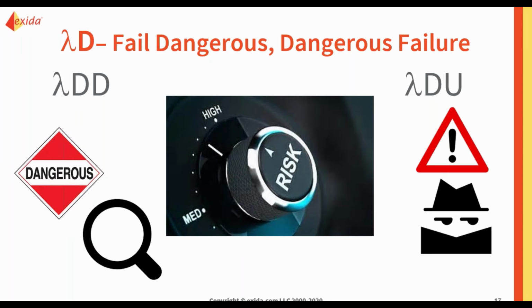What if you have a pressure sensor that is not working and it's high pressure, supposed to shut down the system? It goes over that pressure, you don't know about it. You could have a valve getting stuck in an open on-trip application. It hasn't been used in too long, corroded shut. It needs to close, can't. What about a transmitter shorting? So all of these could be dangerous detected or undetected depending on your diagnostics.